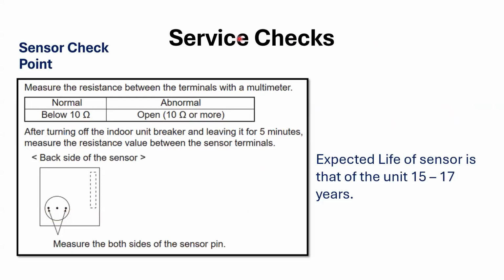Service checks. So again, back to that sensor. If you have a problem with that sensor, then you need to do some testing on it. So measure the resistance between the terminals with the multimeter. So again, disconnect it from the board, right? We're doing continuity testing. Get it disconnected from the board when you're doing this. And it's pretty basic. Less than 10 ohms is going to be normal. If it's open or 10 ohms or more, that's abnormal.